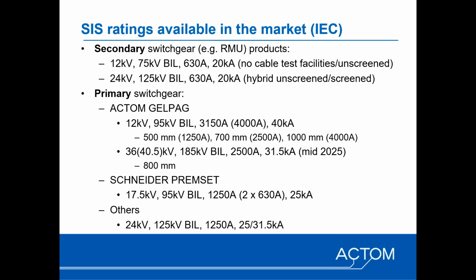Right, so I mentioned that what we've really seen is that the boundaries and the ratings of solid dielectric switchgear are really being pushed. Just focusing in on the Actom GelPag switchgear, we've mentioned other examples here, but currently we have a 12 kV, 95 kV solution rated all the way up to 4,000 amps. We put the 4,000 amps in brackets because that requires forced cooling; it can effectively operate at 3,150 amps without forced cooling. And that's quite significant because of the losses.